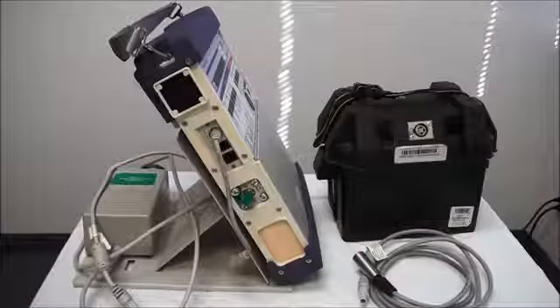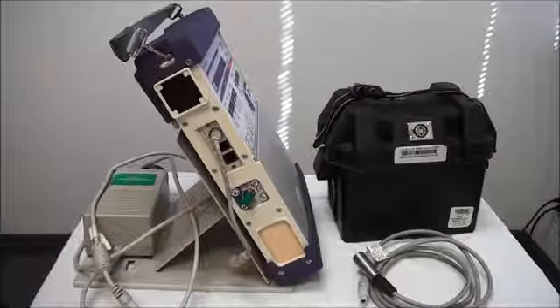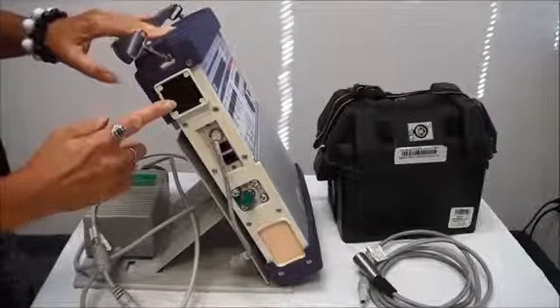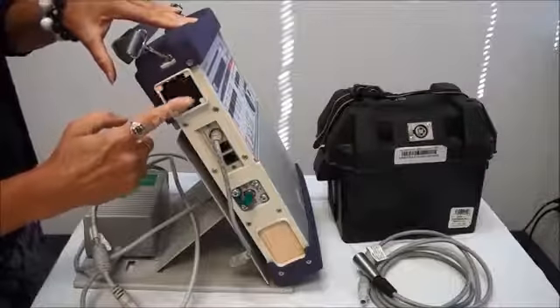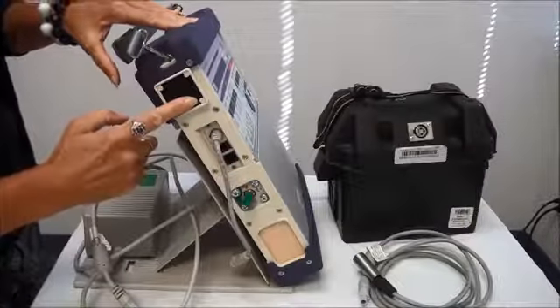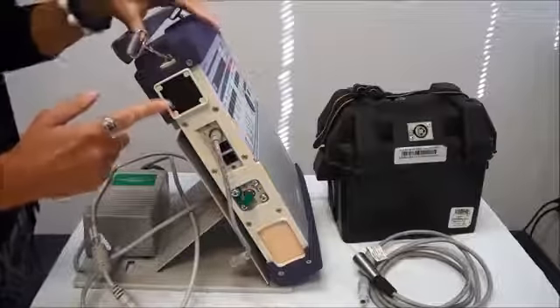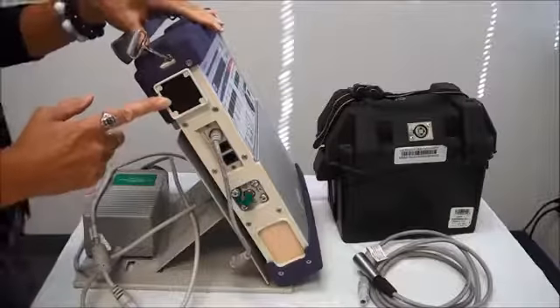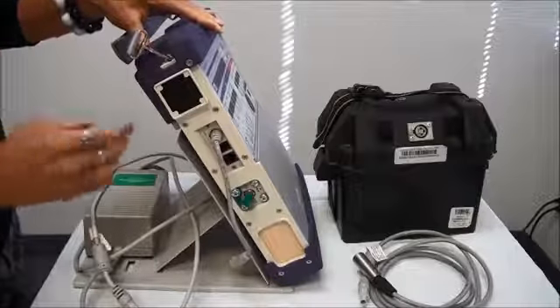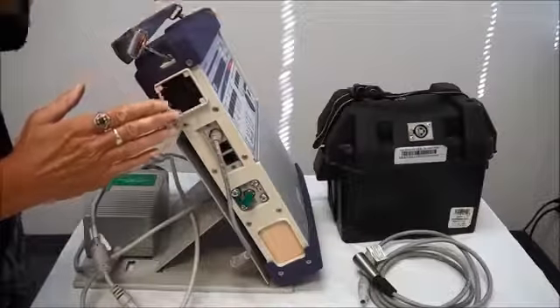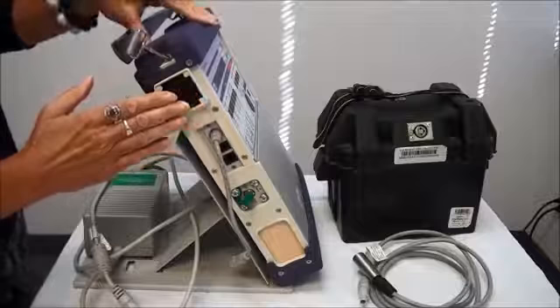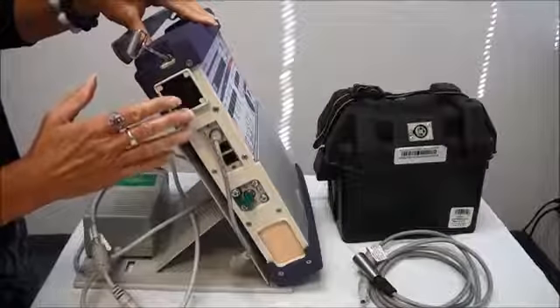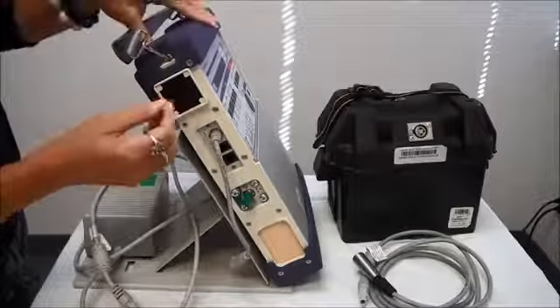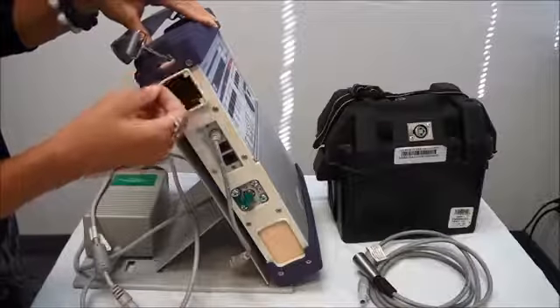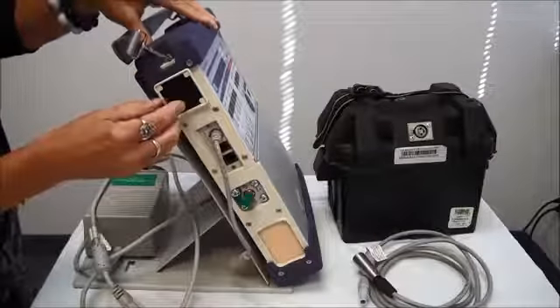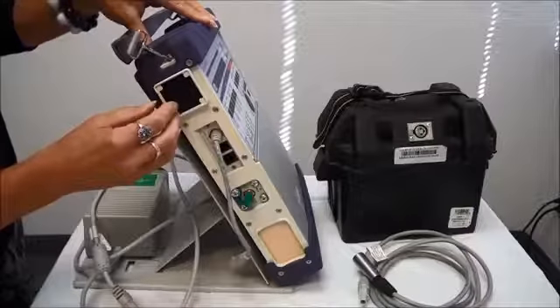Okay, now we're going to take a look at the right side of the ventilator. On the very top of the right side, you have a filter, and there's a cover that goes over the top of the filter. This filter needs to come out approximately once a week to be cleaned, or more often if necessary. You want to be careful when you're taking the filter out because there's a cover that snaps in over the top. And you want to be careful when you're taking the cover off that you're not using anything to poke in there like a pen or a screwdriver or anything like that, because if you do that you can do damage to what's behind the filter.